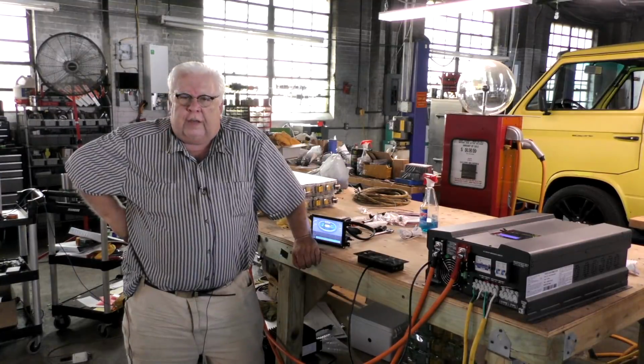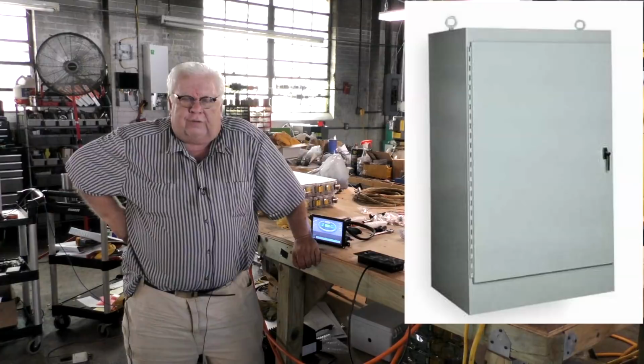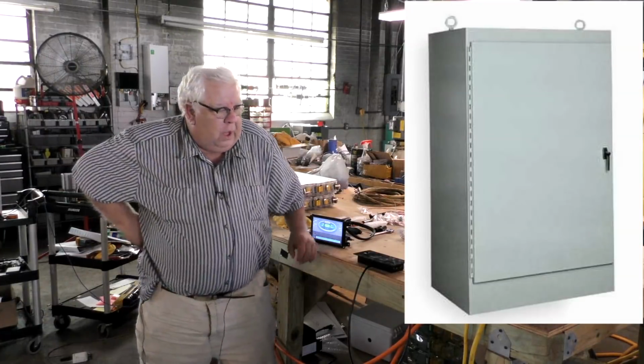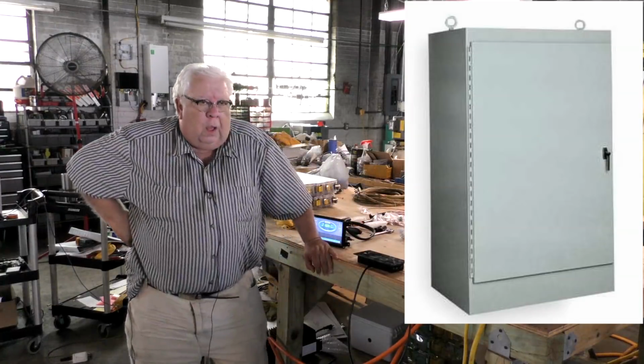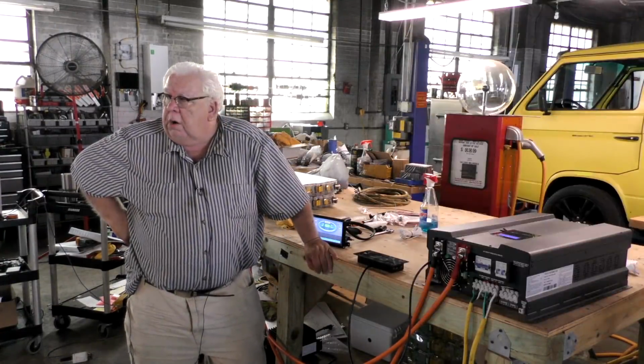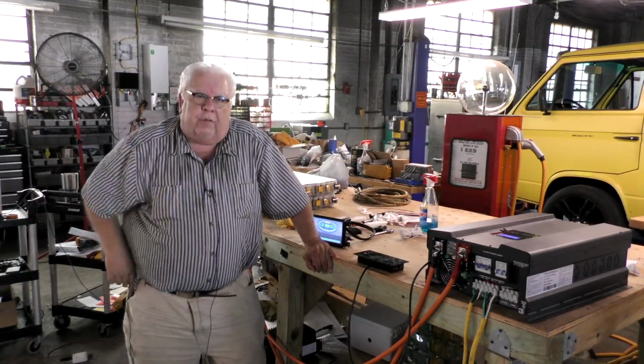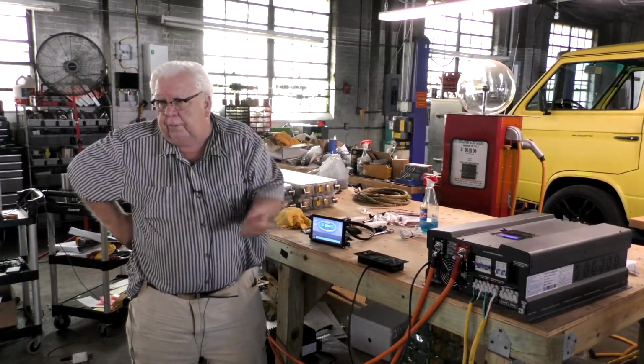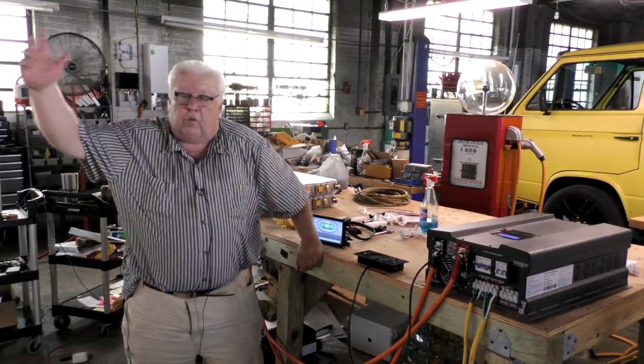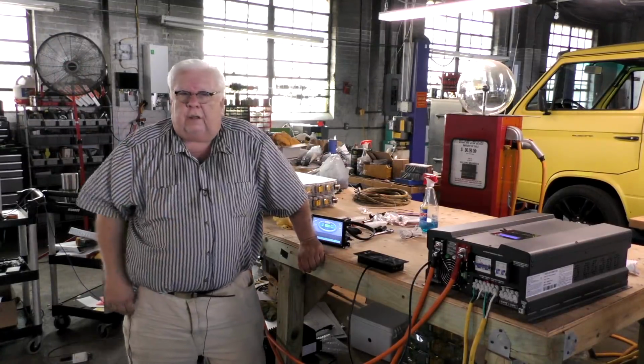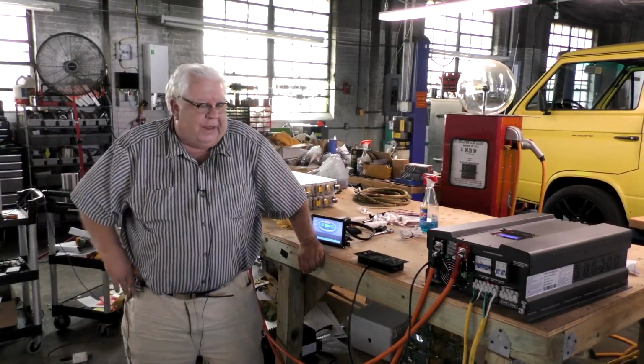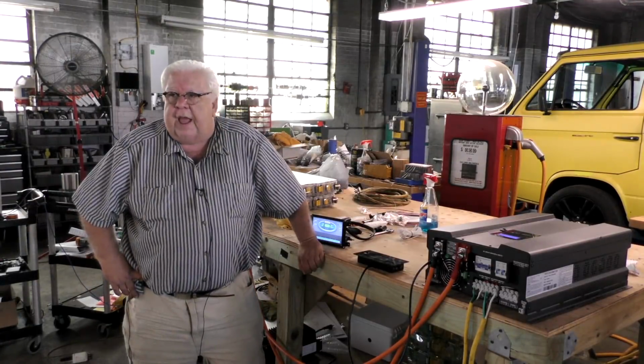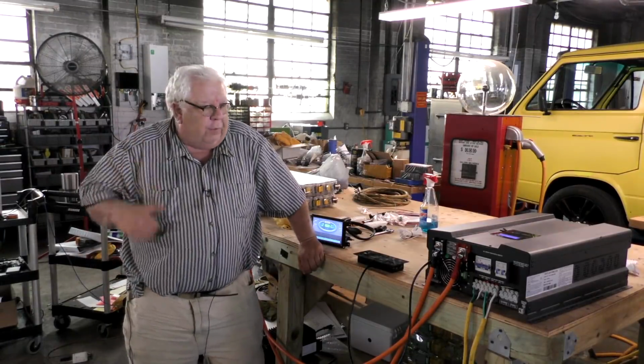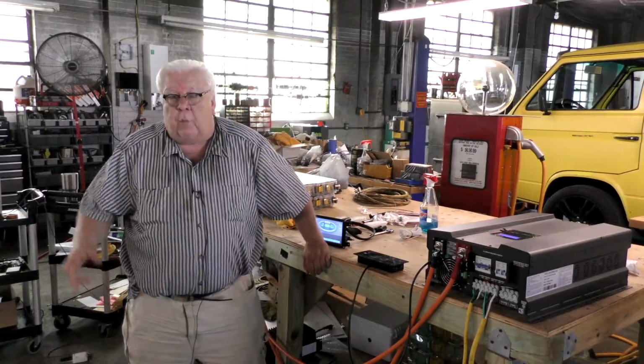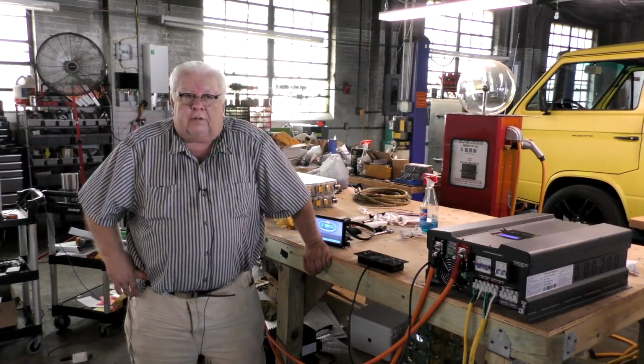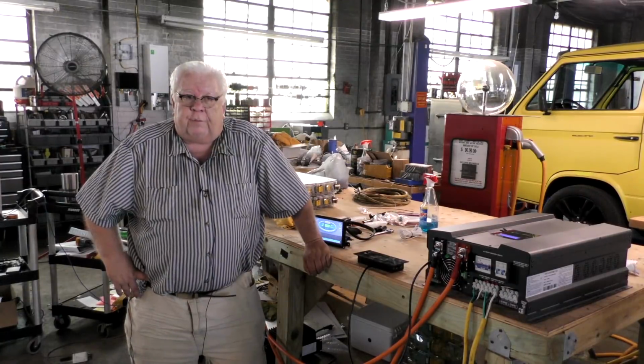And we're going to get a large Wiegmann 72-inch cabinet, put 16 Tesla battery modules in it. This inverter, a contactor to shut off our grid tied, and you bring your grid right down into the enclosure, and your grid tied photovoltaics right into the enclosure, and then you'll have an output to your loads panel in your house.